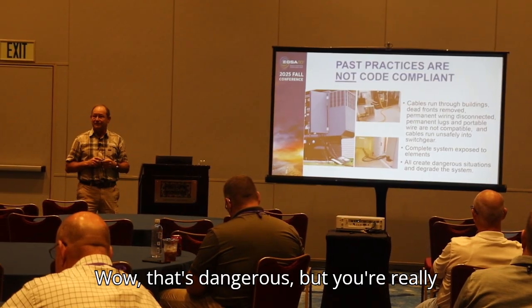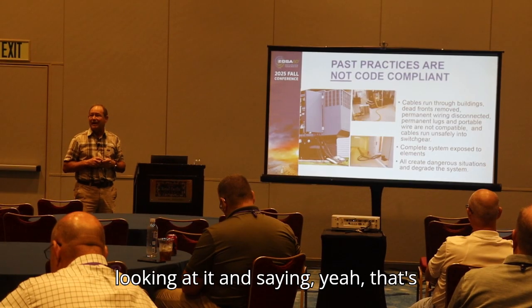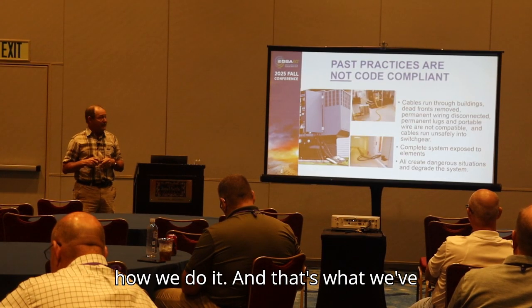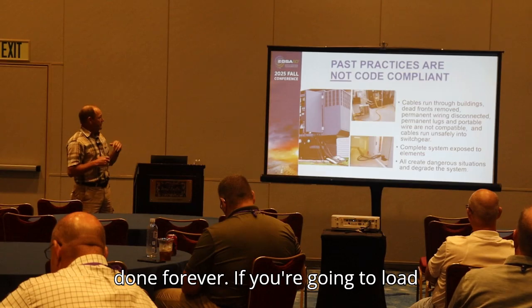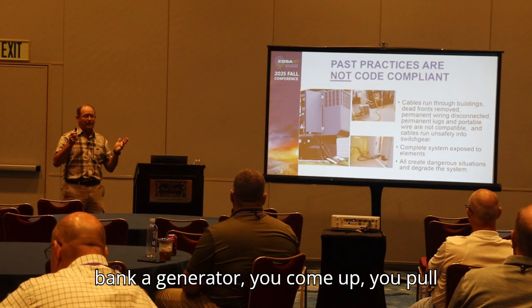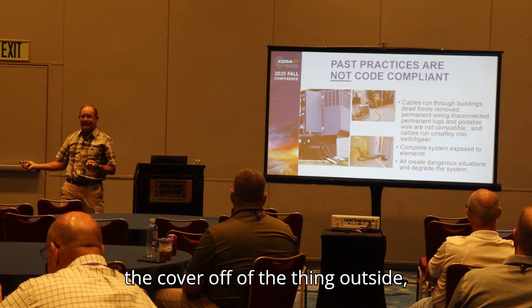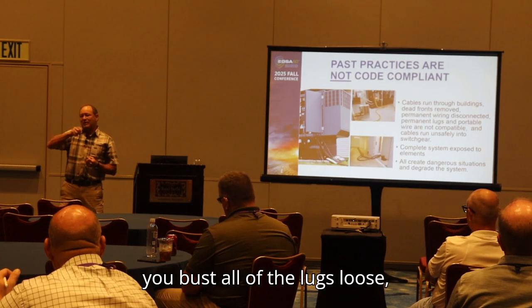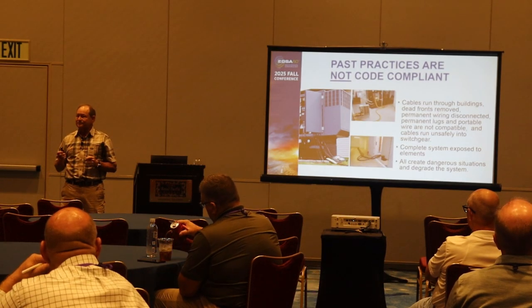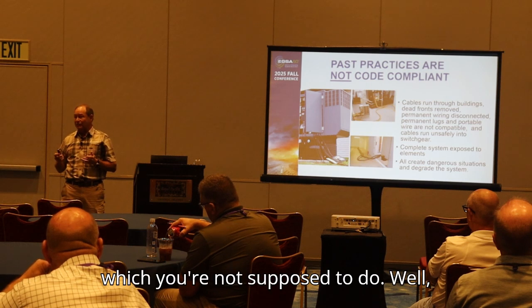Wow, that's dangerous. But you look at it and say, yeah, that's how we do it, that's what we've done forever. If you're going to load bank a generator, you come up, pull the cover off the thing outside, and bust all the lugs loose, which you're not supposed to do.